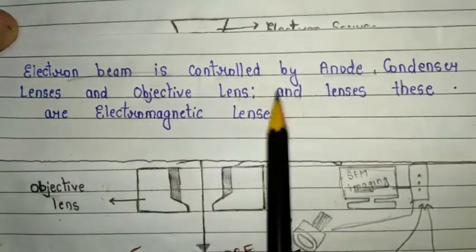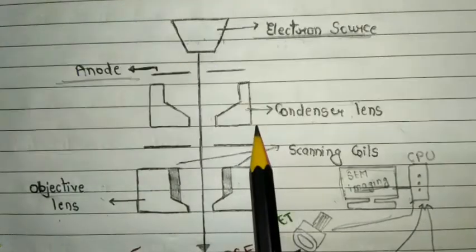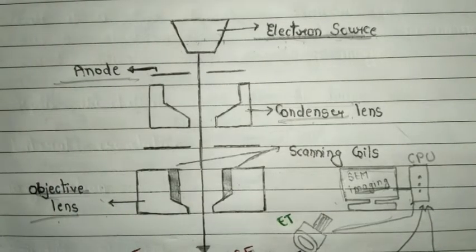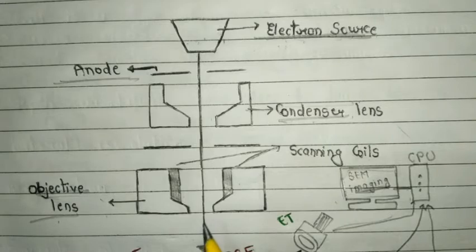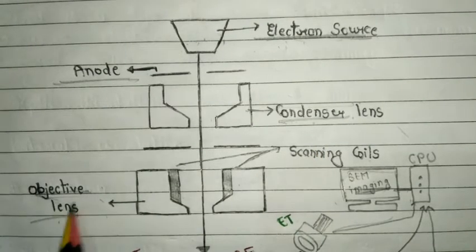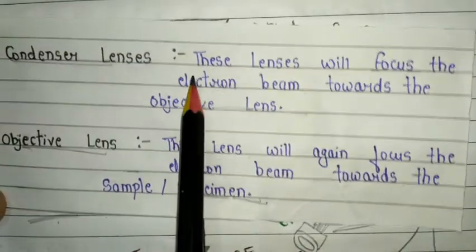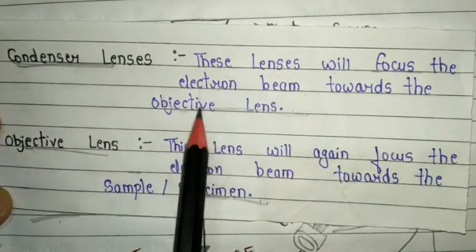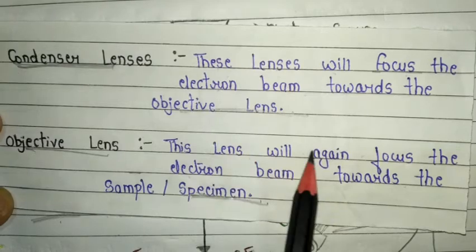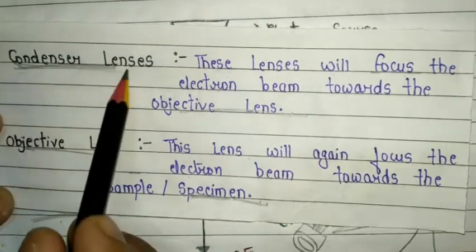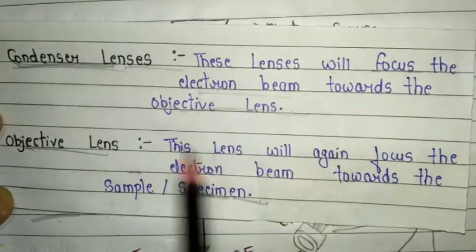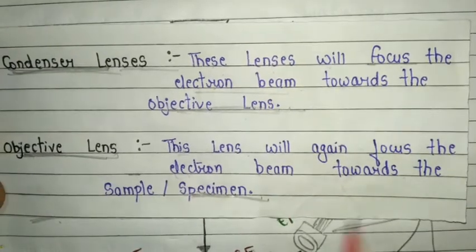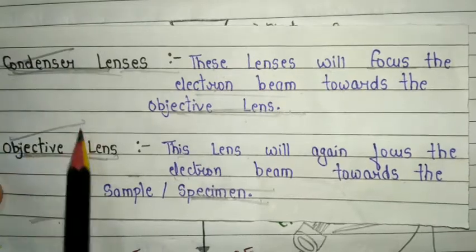Condenser lens and objective lens are electromagnetic lenses. Two types of lenses are used: condenser lens and objective lens, and both are electromagnetic lenses. The condenser lens focuses the electron beam toward the objective lens. So after the electron gun produces the electron beam and the anode accelerates it, the condenser lens focuses the beam toward the objective lens. Then the objective lens again focuses the electron beam toward the sample specimen.